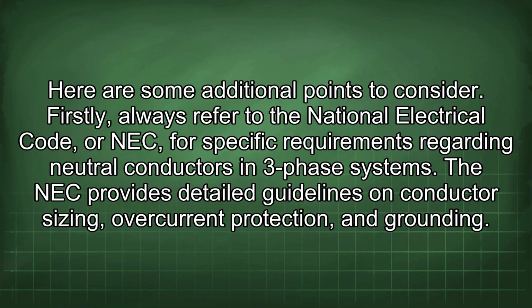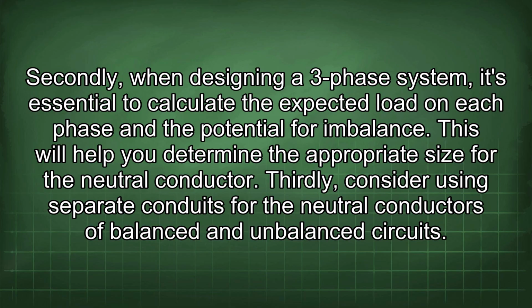Here are some additional points to consider. Firstly, always refer to the National Electrical Code, or NEC, for specific requirements regarding neutral conductors in 3-phase systems. The NEC provides detailed guidelines on conductor sizing, overcurrent protection, and grounding. Secondly, when designing a 3-phase system, it's essential to calculate the expected load on each phase and the potential for imbalance. This will help you determine the appropriate size for the neutral conductor.